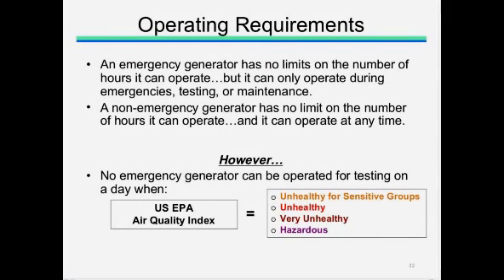In regards to operating requirements for stationary generators within the model rule, it does not include restrictions on the number of hours a generator may operate. Instead, the model rule just states that an emergency generator can only operate for emergencies or testing or maintenance. However, an emergency generator cannot operate for testing on a day which has been classified by the state or local air quality agency as unhealthy for sensitive groups or greater on the US EPA Air Quality Index.